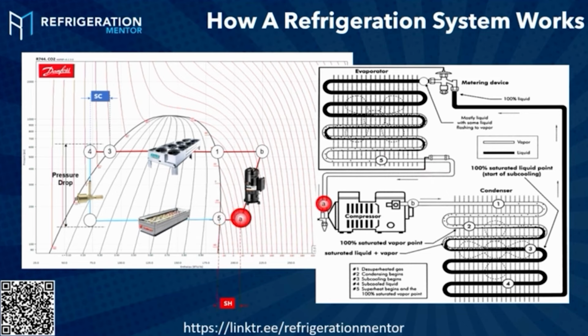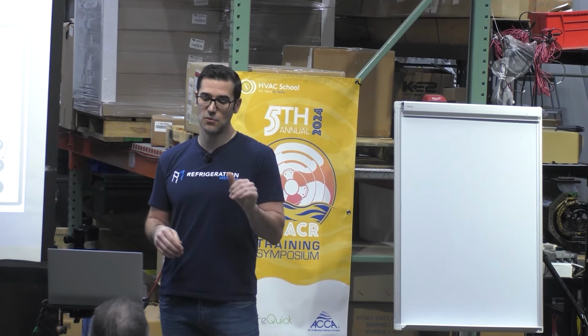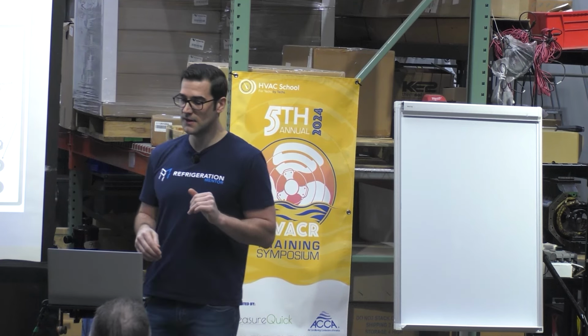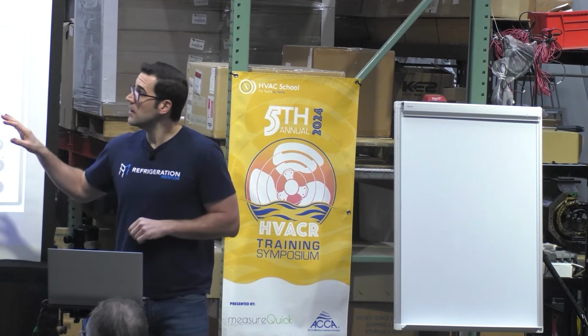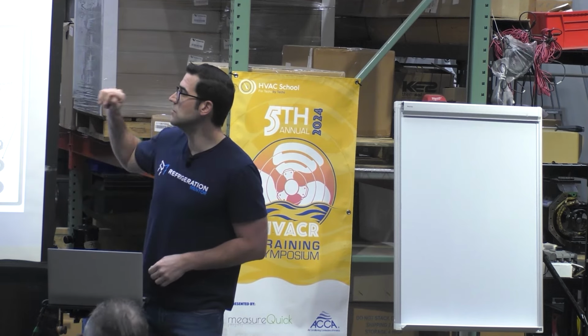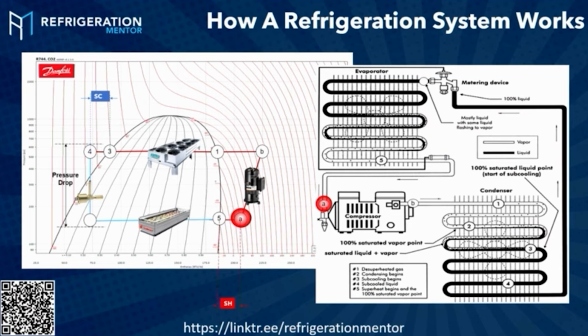This is your superheat. So you have evaporator superheat, and you have compressor superheat. You always want to make sure that you, once again, do dew point when you're using blended refrigerants. And there's going to be people who tell you, no, you got to use midpoint, but we're not going to dive into that situation. On this diagram, this refrigerant, what is it? I'm using CO2 as a refrigerant.